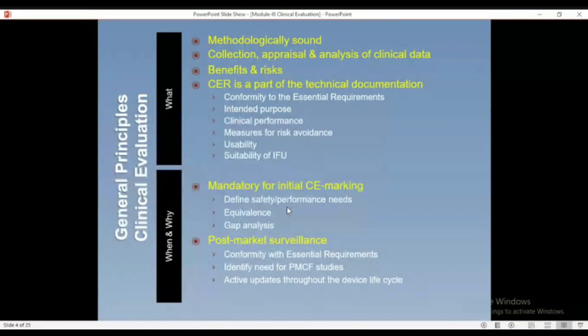This is required: gap analysis. Gap analysis means that between the devices in the market and the device you developed, if there is any gap in technology or in safety, we analyze that and try to cover it. For that also, it is important. Gap analysis is also like this: I am using ISO 13485, suppose 2012, and now the standard is 2016. So what is the gap between that standard and the current standard? That is also done in gap analysis.